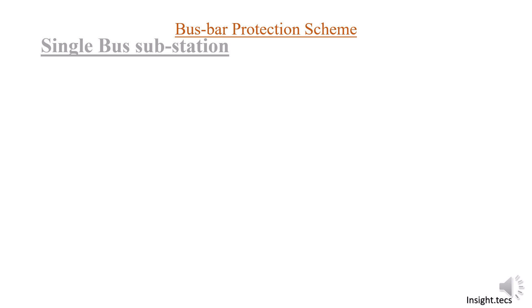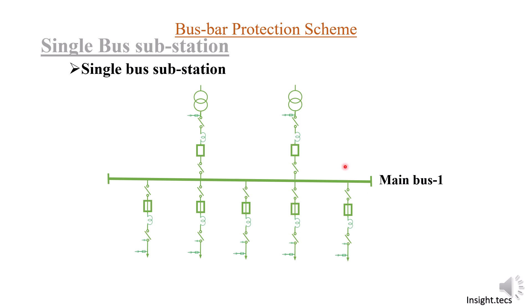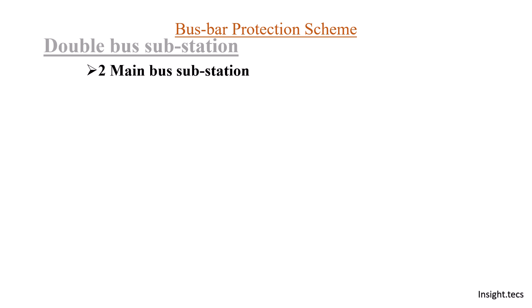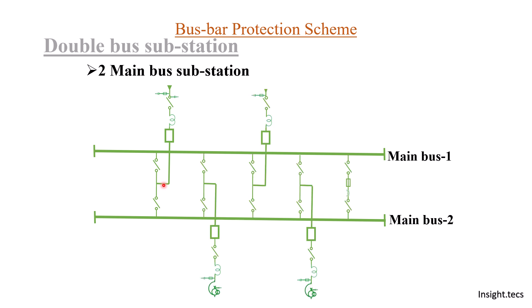In today's video we will be learning about how to use a two bus substation as a three bus substation — how we can get the benefits of a three bus scheme using just two buses. For the single bus scheme we have already considered main bus one with all feeders connected to it. For the double bus scheme with two main buses, both buses are connected with a selector isolator so you can select the bus to which you want to connect a particular equipment.